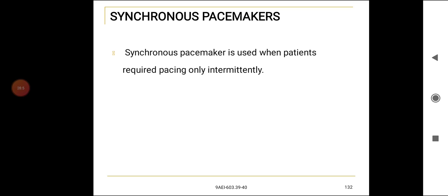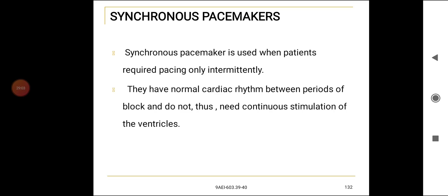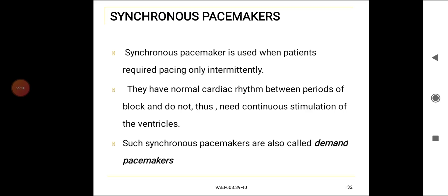Synchronous pacemakers. Synchronous pacemakers are used when the patient requires pacing only intermittently. They have a normal cardiac rhythm between the periods of block and thus do not need continuous stimulation of the ventricles. Such synchronous pacemakers are also called demand pacemakers. When demand arises, only then is it used. So it is an intermittent or non-competitive pacemaker.